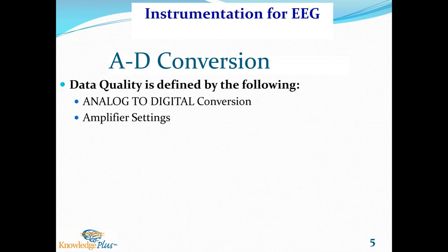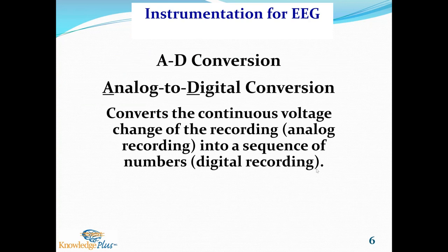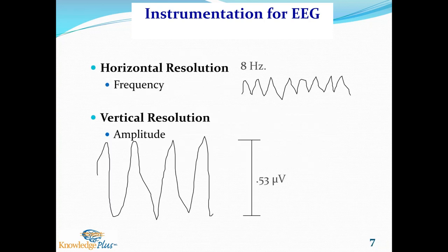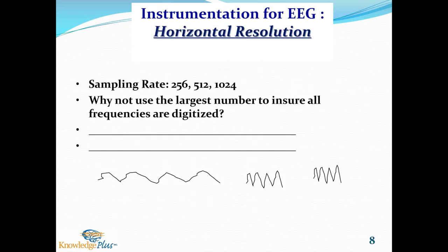So we don't really have brain waves. We have brain activity, we have neurophysiologic activity, but there's a process in taking that activity and converting it into a waveform. So data quality, how much does the EEG waveform look or replicate what's really happening in the brain? That depends on your amplifier settings and your A to D conversion settings. So the definition of analog to digital conversion is the method by which your instruments convert the continuous voltage change of the recording into a sequence of numbers, or digital recording. There are two characteristics of A to D conversion, two quality factors. One is horizontal resolution. That impacts our frequency resolution, and then vertical resolution impacts our amplitude resolution.